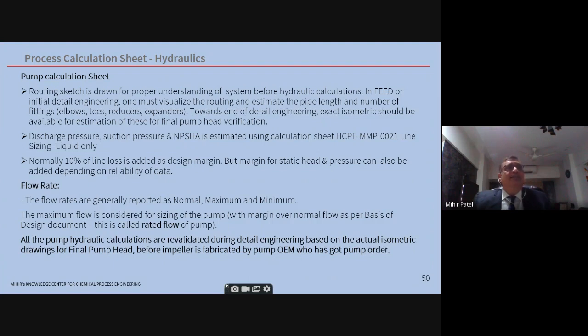Then the flow rates are there. So the flow rates are generally reported as normal, maximum, minimum. These are very much required for the control valve. The control valve has to calculate the Cv at 3 different points: minimum, normal, maximum. And the last point, again I have mentioned here, all pump hydraulics have to be revalidated against the actual isometrics later on in detail engineering, so the final impeller head can be established.